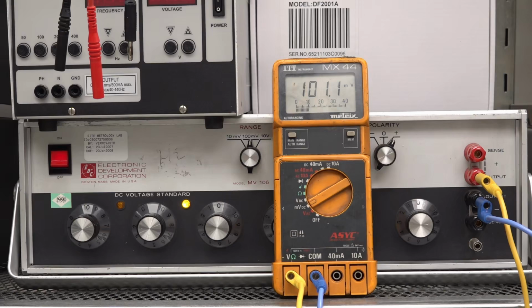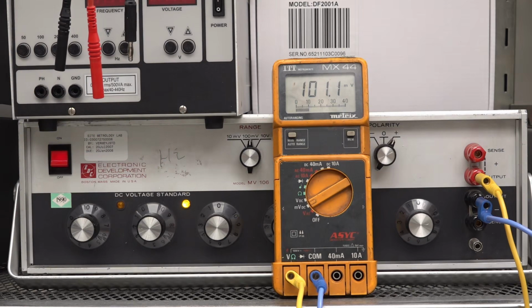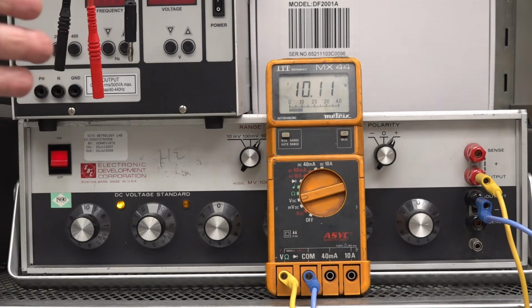So if I hook it up to my lab reference here, I've got it set to 100 millivolts. And of course my MV106 here has gone to a standards lab and been compared. It's good enough to calibrate a 6.5 digit meter, let alone a 4,000 count meter like this one. So it's 1.1% out. That's out of spec. And we can change the various ranges as well. It's the millivolt range in DC, exactly the same, bang on to the least significant digit. It's also 1.1% out for the 10 volt range. And that's the same for the ohms as well, and I believe for the current as well. So it looks like one of those trimmers is going to be the absolute tweaking, but I don't know which one.